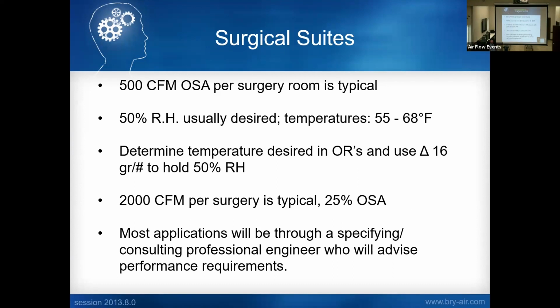The trouble is where you're going to put the dehumidifier, because you have to get your supply and outside air in and out. In existing hospitals, the plenum space, the ductwork and all that above the drop ceiling is very limited, so it does become a challenge on these types of projects.